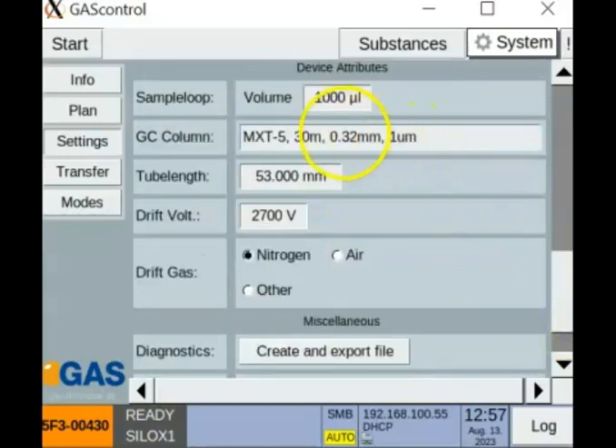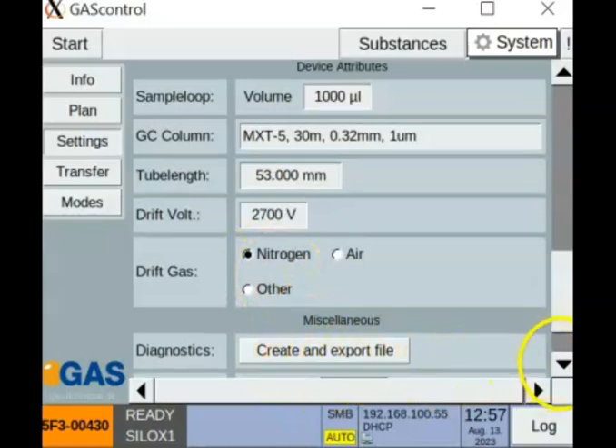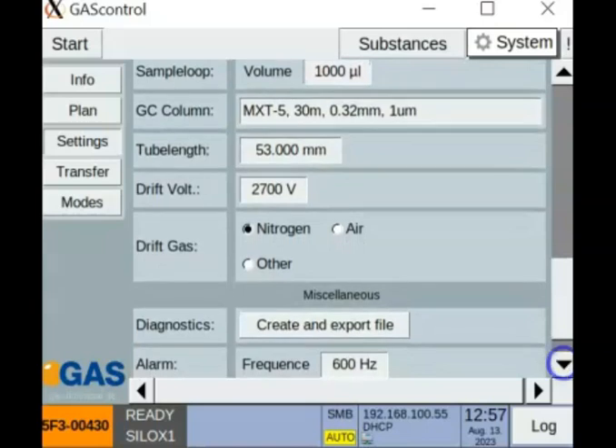Furthermore, there is the information of the GC column or the sample loop and the tube length of the IMS drift tube, the drift voltage, and the fact that we are operating the instrument with nitrogen. Very important, if there is a problem with the instrument, it is possible to create and export the diagnostics file and send it to gas support. Also possible is to have a look at the log, the system log.